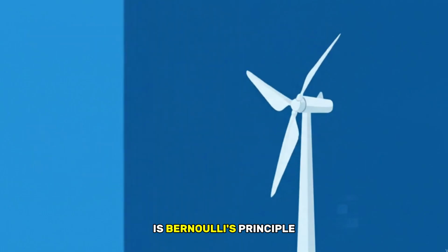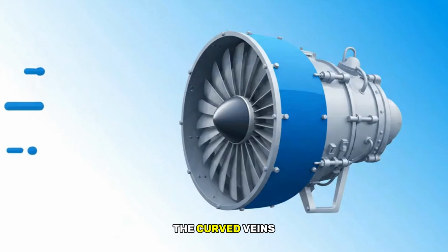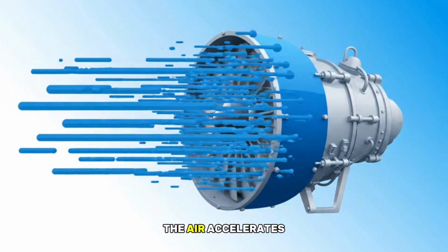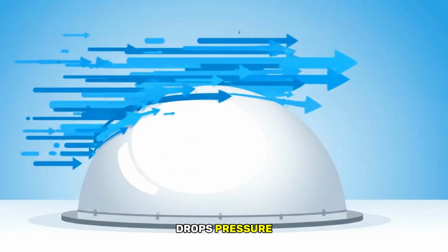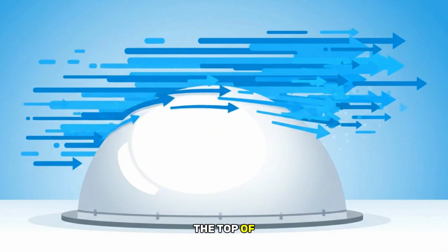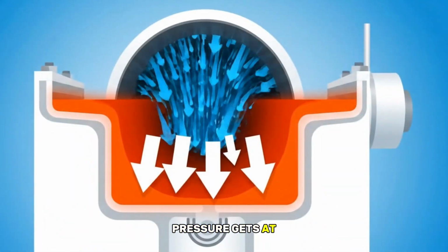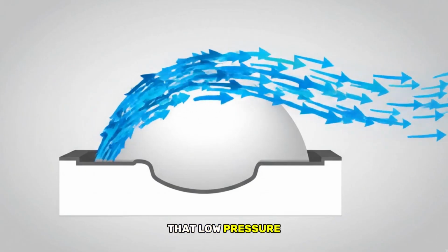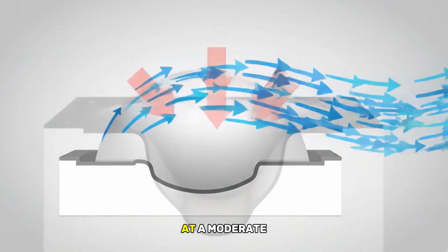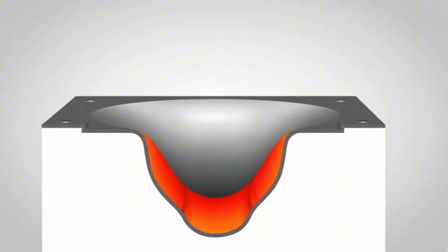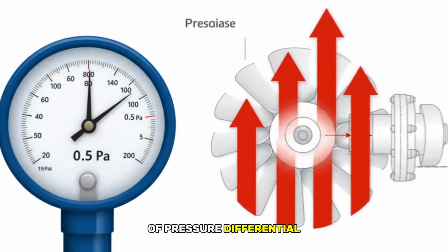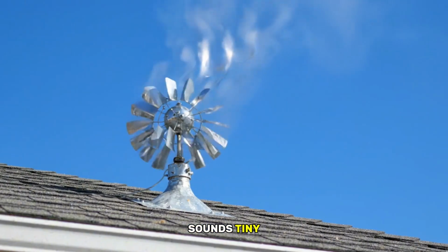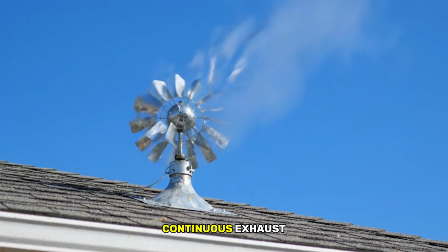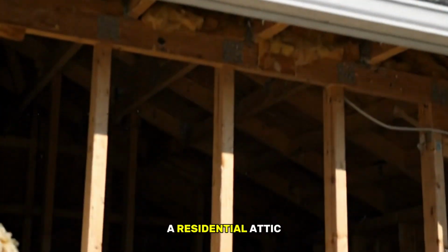The first force is Bernoulli's principle. When wind hits the curved vanes of the turbine, the air accelerates around the cowl, and accelerated air drops pressure. The faster the air moves over the top of the dome, the lower the pressure gets at the throat of the turbine. That low pressure acts like a vacuum on your attic. At a moderate 10 miles per hour wind, you get about half a pascal of pressure differential, pulling hot air up and out through the turbine. Half a pascal sounds tiny, but it's enough to keep a continuous exhaust stream moving through a residential attic.